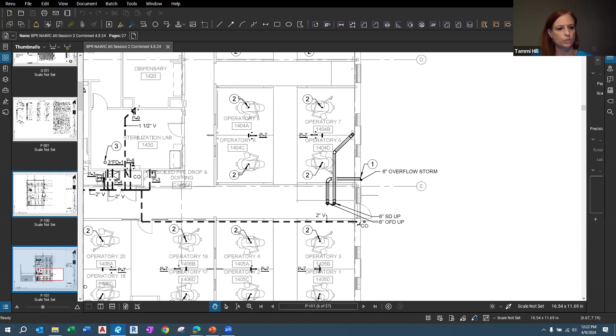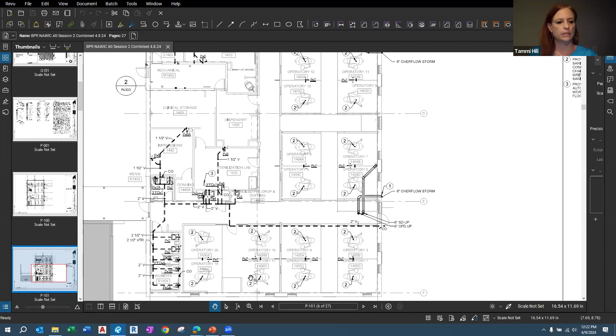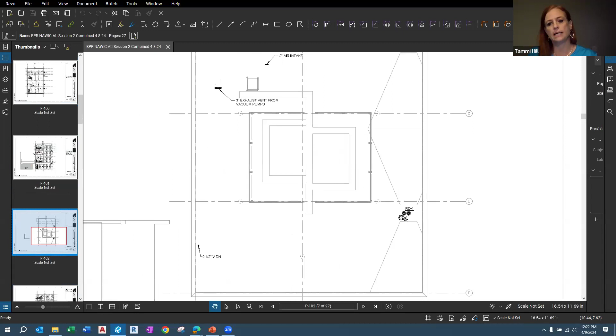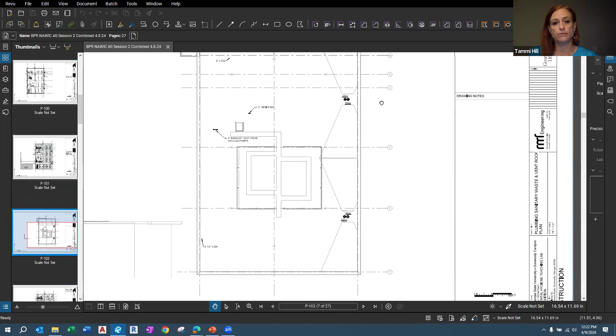You'll also see a big 6-inch drain, which we can see on our sanitary plan underground. What is that? It's not a vent line, it's not dashed, it's not shown like the vent lines, but it says it's an overflow storm. So that storm is my first clue it could be related to roof drainage. If I go to the roof plan, sure enough, we've got some roof drains up on the roof, it looks like two on this plan. When you have a roof drain, you'll typically find some kind of overflow related to it too, because if the roof drain clogs, the water needs somewhere else to go.